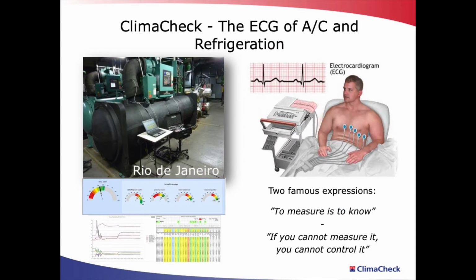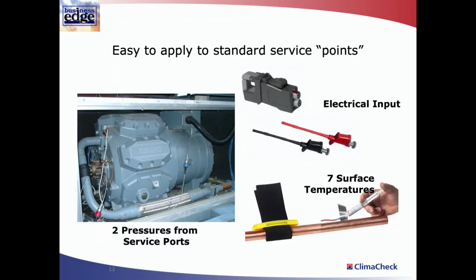It's effectively a product that's very much like a doctor approaching your body to determine your well-being. The compressor, effectively your heart, is measured in terms of high and low pressure, power input, and so on. Key temperatures are taken around the system, and the power input to the compressor is used to calculate the mass flow of refrigerant, thereby enabling ClimaCheck to tell you exactly what the chiller is doing, or the VRF system, giving you cooling capacity, power input, power factor, heat of rejection, volts per phase, amps per phase, subcooling, superheat, refrigerant charge indication, and even telling you if your water flow or airflow values are in the right region or not.